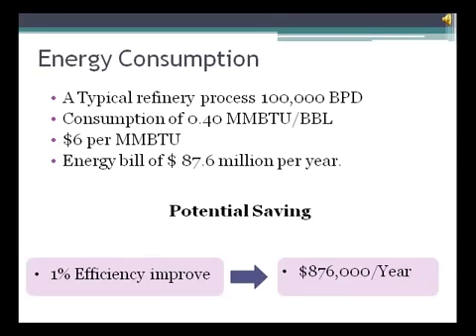In a typical refinery, two-thirds of the operating cost is fuel cost. For example, if we have a regular size refinery processing 100,000 barrels per day, with a typical energy pricing of $6 per million BTU and requiring 0.40 MMBTU per barrel of crude, the energy bill will be $87.6 million per year. Increasing the total fuel efficiency by only 1% can translate into savings of almost $1 million per year.